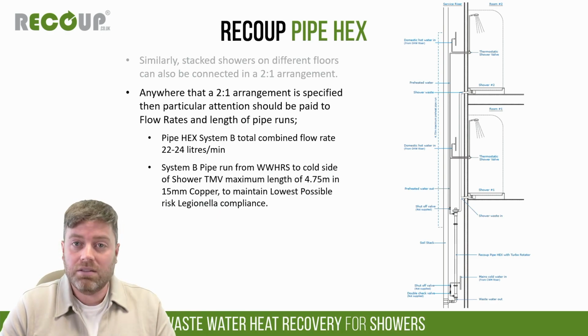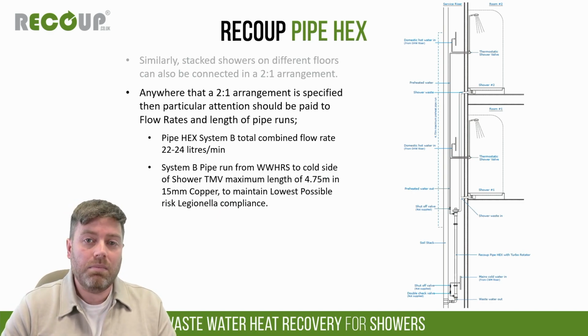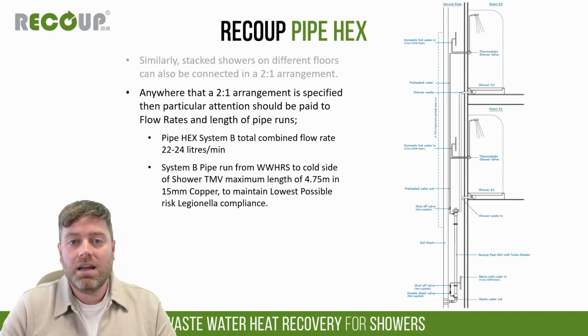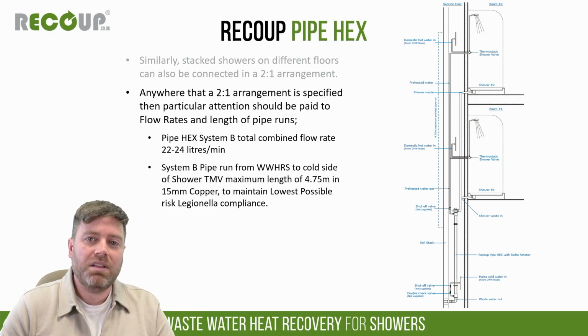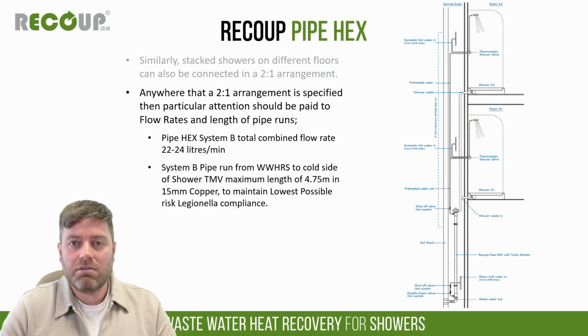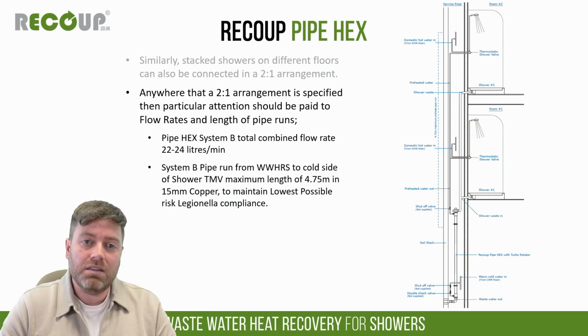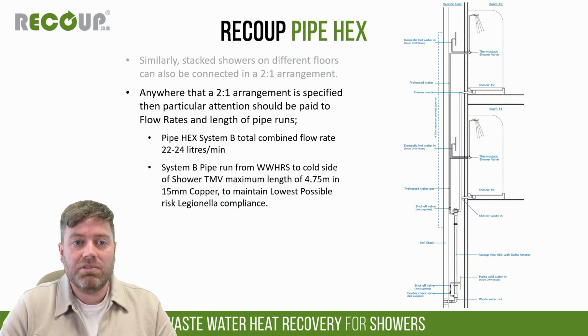On Legionella, it always gets asked about with wastewater heat recovery. All of the products and all of the system types we have are independently Legionella control risk assessed. So we heat the water to around 25, 26 degrees, something like that, so it's at the low end of the Legionella growth range. As long as they're installed within the recommendations, each of the products and the installation methods are considered lowest possible risk. As I say, we have those Legionella control risk assessments we can supply. If you go outside of those, then it just means needing to risk assess it separately. But they're considered lowest possible risk if installed within our recommendations. There is no zero risk with Legionella. Lowest possible risk is as low as you can get. But as I say, it's something that always does get asked with wastewater heat recovery.